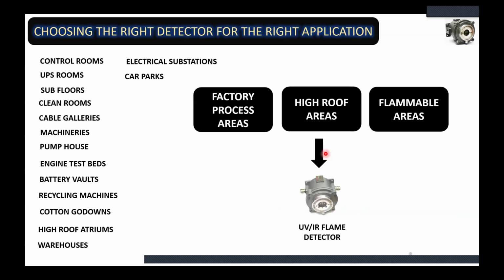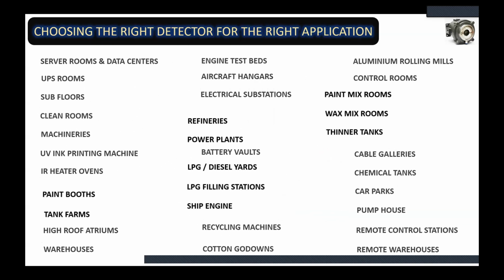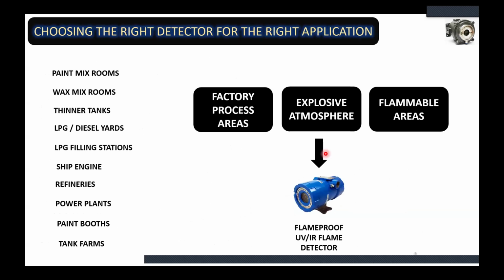These are some of the factory process areas, high roof areas, and flammable areas, like control rooms, UPS rooms, pump houses, engine test beds, battery rooms, cotton godowns, warehouses, etc. The best recommended detector would be a UVIR flame detector. Again, factory areas, process areas, explosive atmosphere: paint rooms, wax mix rooms, thinner rooms, LPG and diesel yards, LPG filling stations, refineries, power plants, paint booths, tank farms, all contain highly flammable material with very high calorific value. In that kind of atmosphere, it is recommended to go with a flame-proof UVIR flame detector.